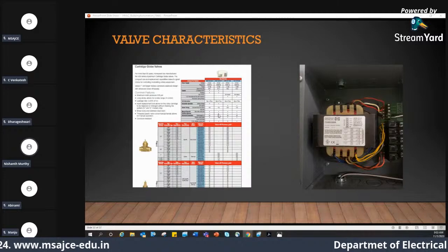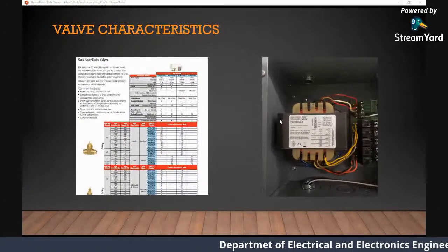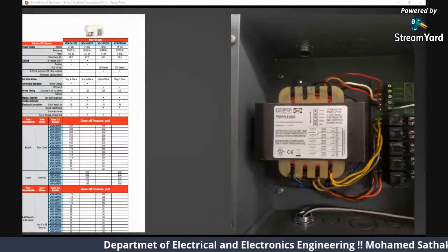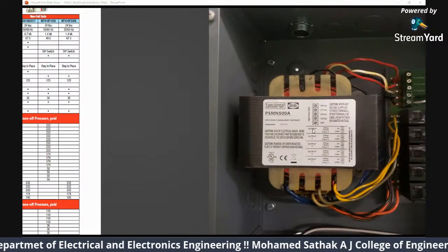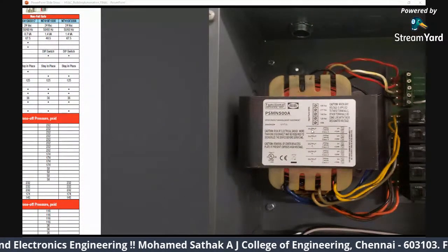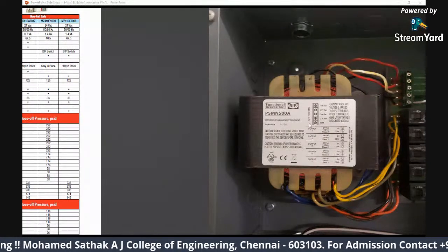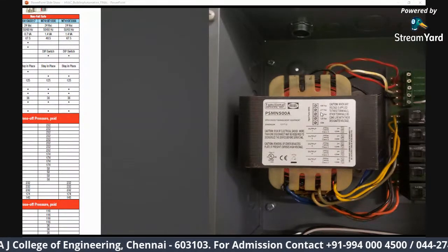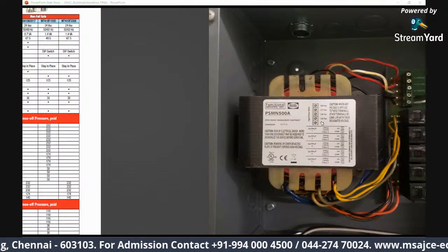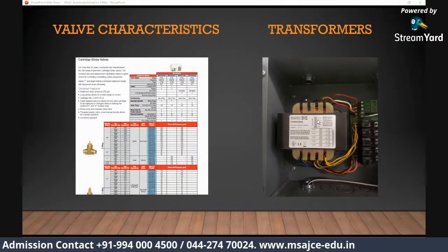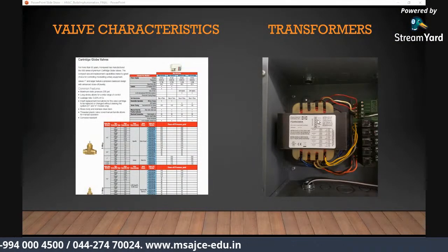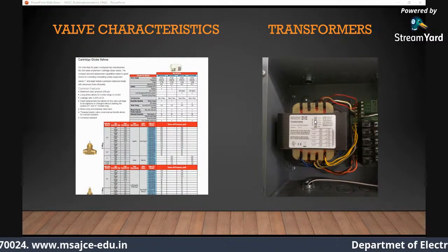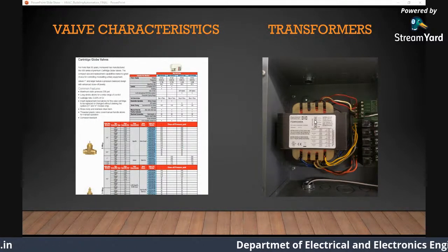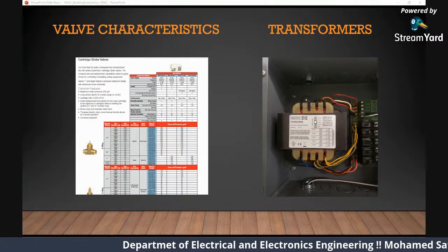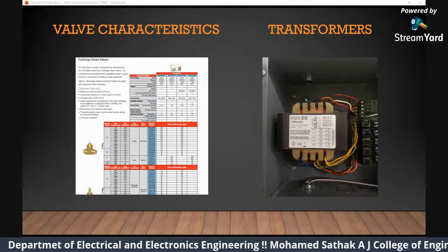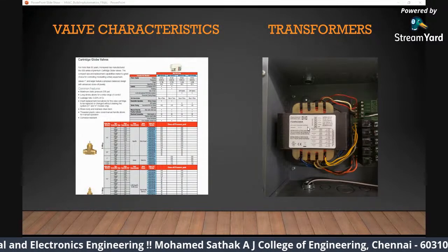This is a transformer. People from an electrical background should know it. So power supply is very important. Any control, any sensor, any pump, everything needs a power supply, right? Without power, you cannot turn on anything. This is a transformer which steps down from, I think, 480 VAC to 24 VAC. So all our controllers, all direct digital controllers, operate on 24 VAC, 24 VDC. As I mentioned, building automation runs mostly on low voltage systems. We never deal with high voltage systems. All your pumps, fans, chillers, boilers run on high voltage systems. So this is your step down transformer.